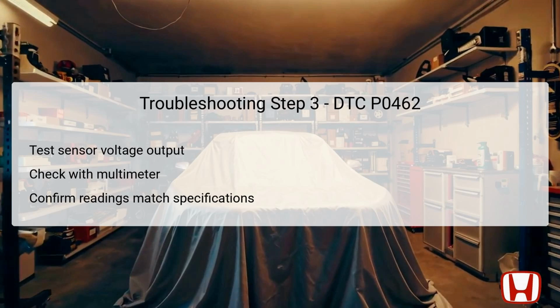The third troubleshooting step involves testing the output voltage of the fuel level sensor using a multimeter. This step is vital, as it verifies whether the sensor generates voltage within the expected specifications. Connect the multimeter to the appropriate terminals of the sensor, ensuring good connections for accurate readings. Once set up, observe the voltage output while the float moves through its full range of motion. The voltage should vary consistently based on fuel levels. If the output remains consistently low or does not align with the specified range, it suggests a faulty sensor that needs replacement. This thorough testing provides clarity on the sensor's functionality and determines the next course of action.